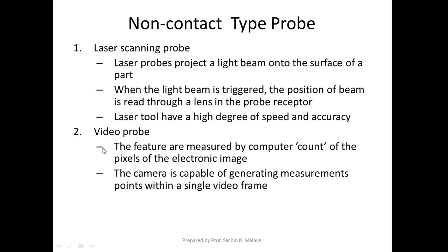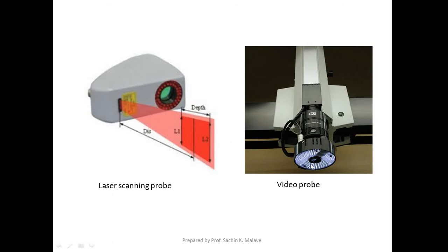Then one more probe is there, that is the video probe. In this probe, the features are measured by the computer count of the pixels of the electronic image. In this case the camera is capable of generating measurement points within a single video frame. So here this is the video probe.